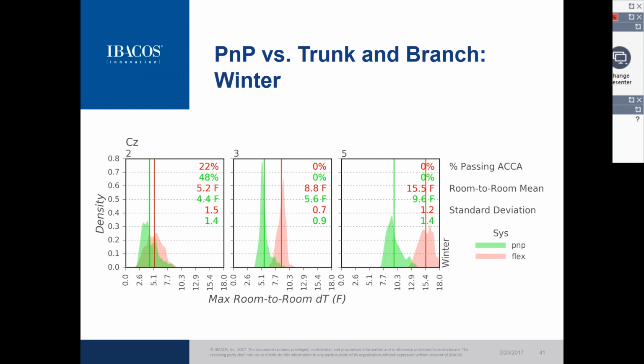However, those types of numbers have been seen in the field before. We've seen up to 10 degrees Fahrenheit room-to-room temperature difference between floors on 3-story townhouses, and a lot of that's driven by stratification and differences in heating and cooling load and needs. On a large townhouse, you might need to deliver the majority of heat to the bottom floor in winter, and conversely almost all the cooling airflow to the top floor in summer. So there's a bigger challenge conditioning these types of houses, especially with these big changes between heating and cooling loads. That's what was driving what's observed here.